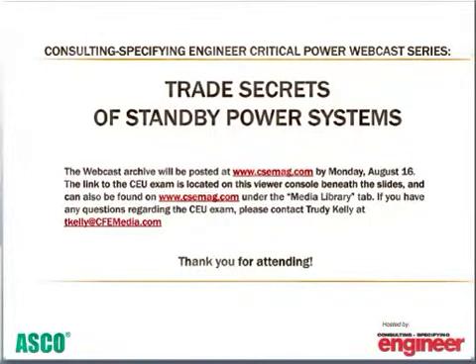Okay, very good. Keith, another question for you from Jim Zavidil from KRS Engineering asking, if you don't have ground fault protection in your system, is there any reason or advantage to using a 4-pole ATS? So usually you don't have a ground fault in your system if it's a small system. For a generator, for instance, if you have a large enough generator, say 750 kW or larger, you've got a 1,000 amp breaker, which requires a ground fault. So in order for the ground fault to work properly, you need a 4-pole ATS.